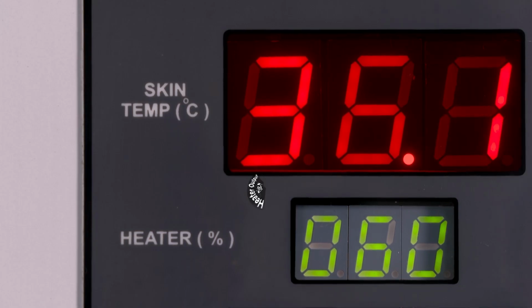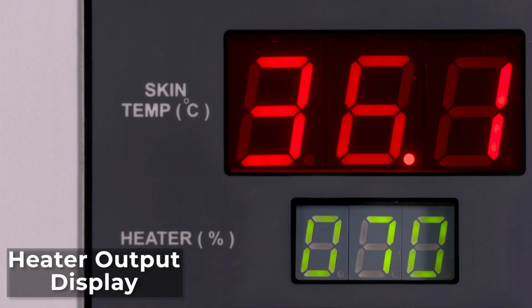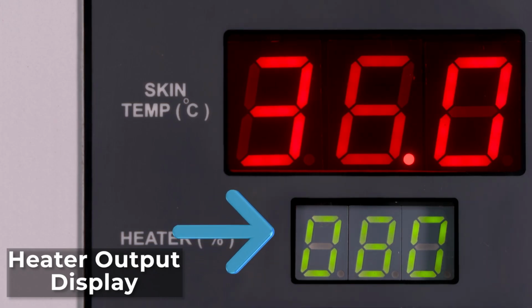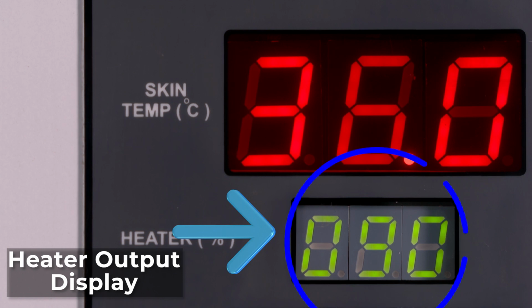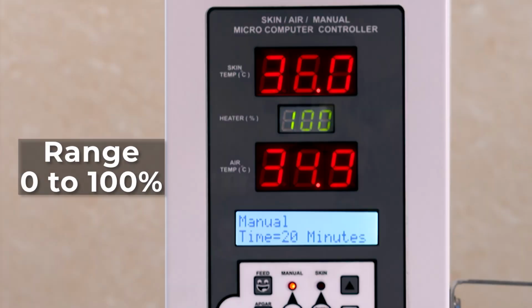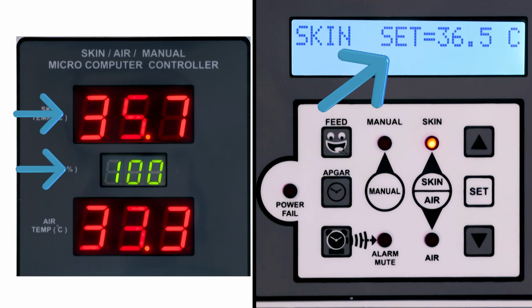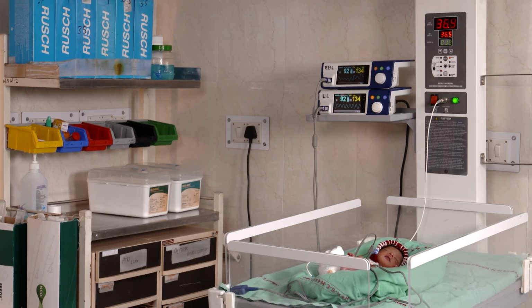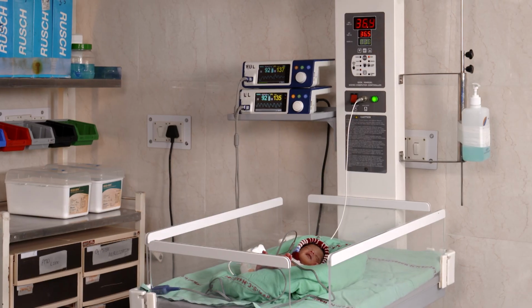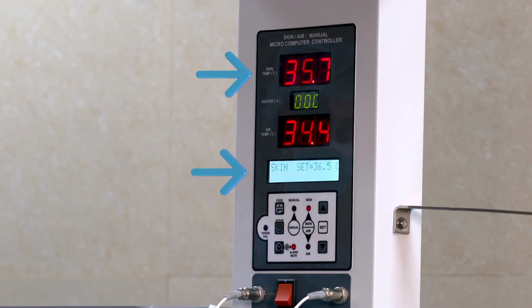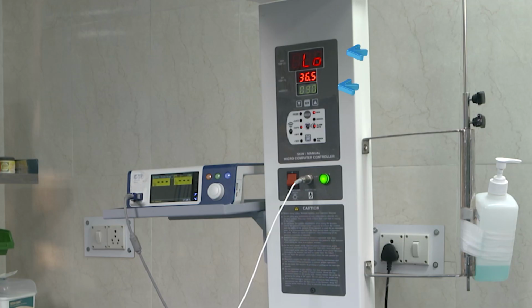The control panel has a heater output display which indicates how much is the heater output of the radiant warmer. It may range from 0 to 100% depending on the set temperature and the baby's temperature. In case the baby is hypothermic and the baby's temperature is less than the set temperature, the heater output will increase automatically, and as soon as the baby's temperature reaches the desired set temperature, the heater output wanes off.